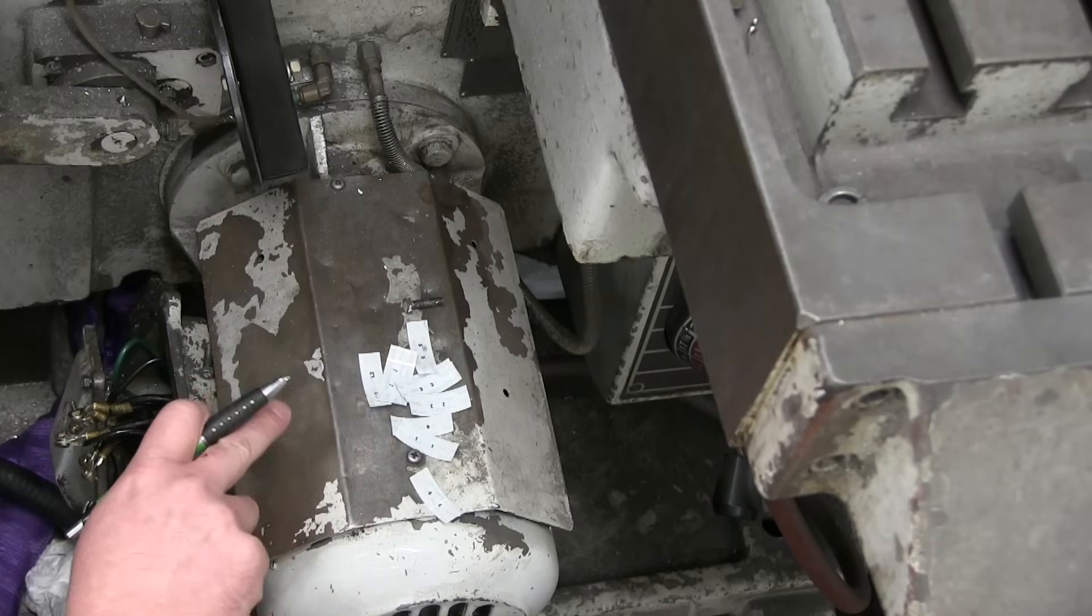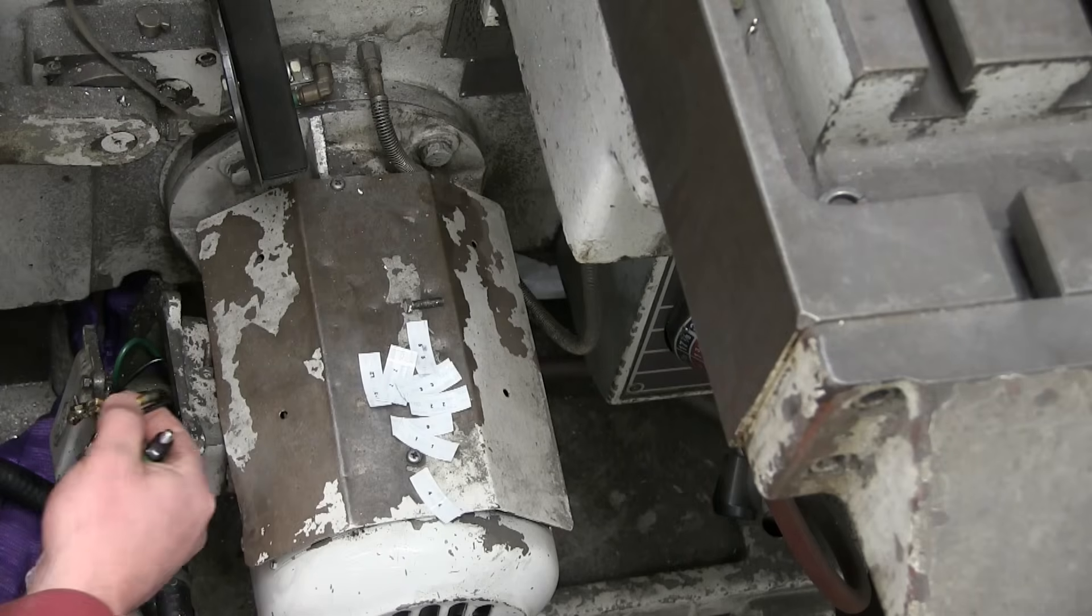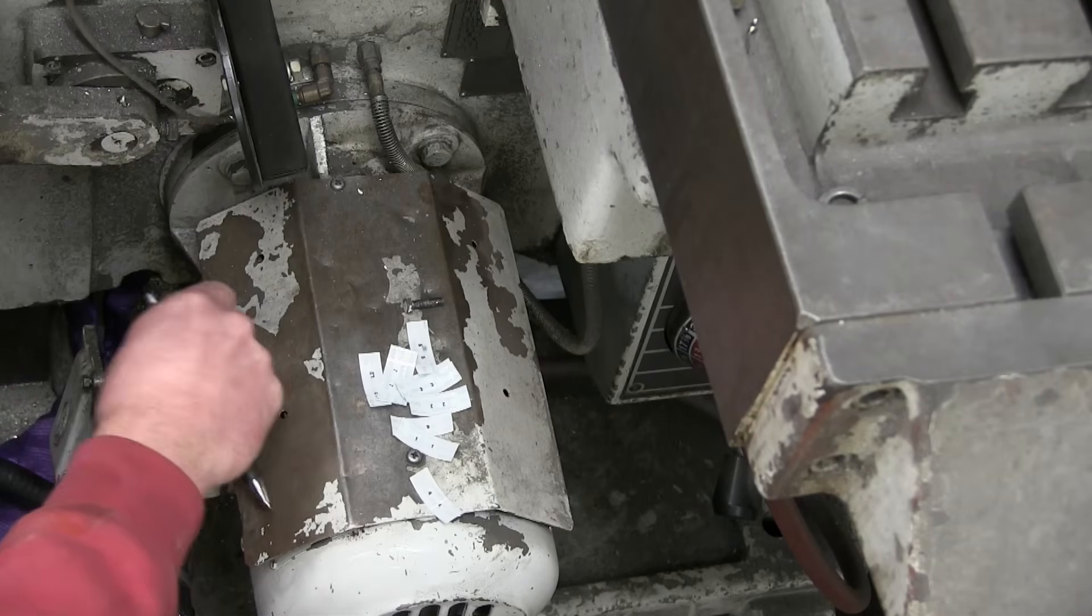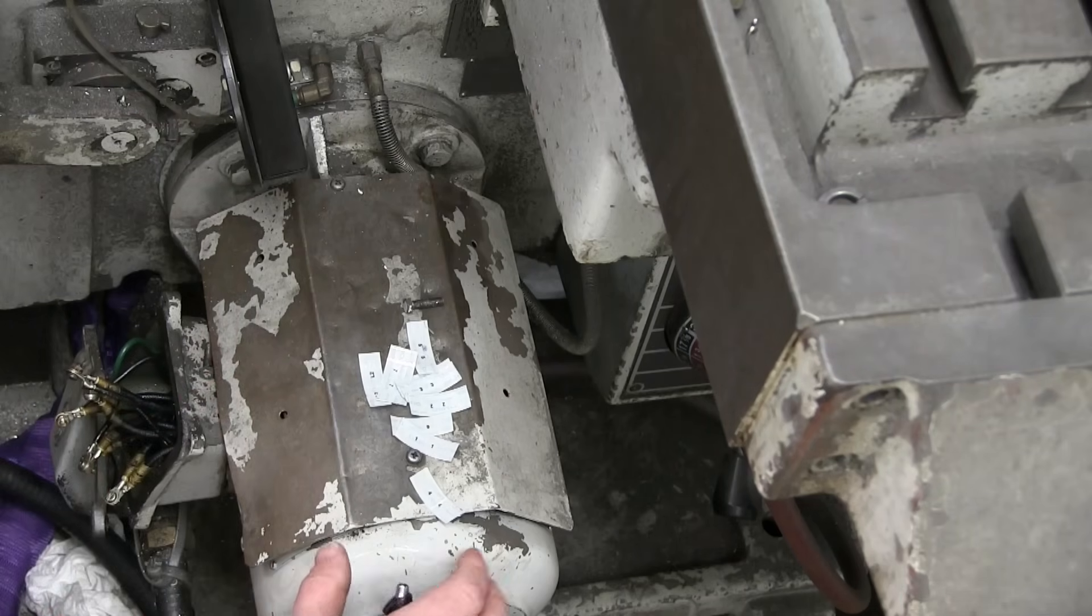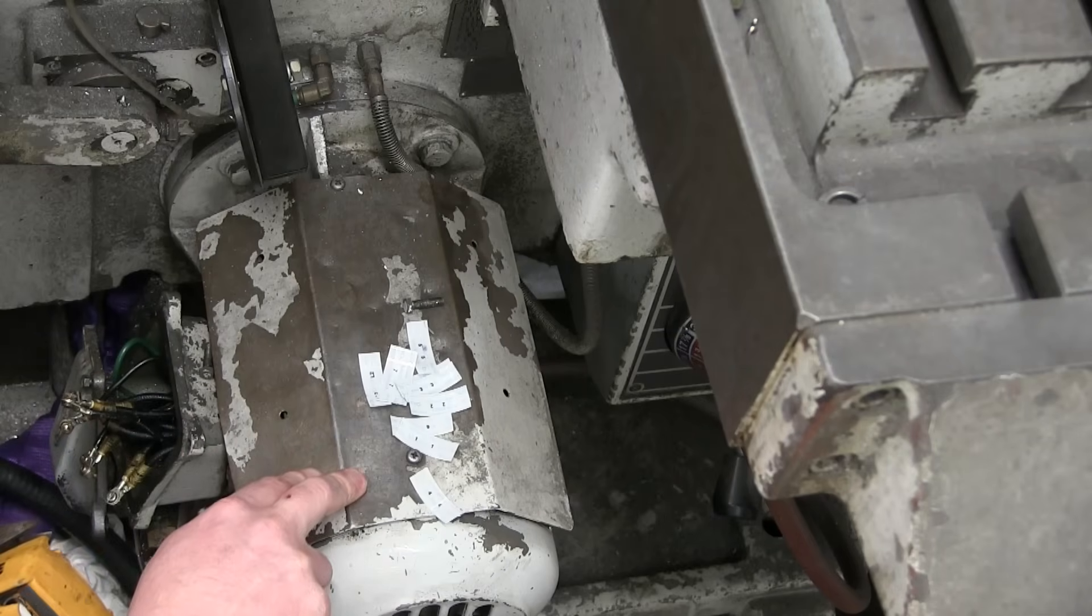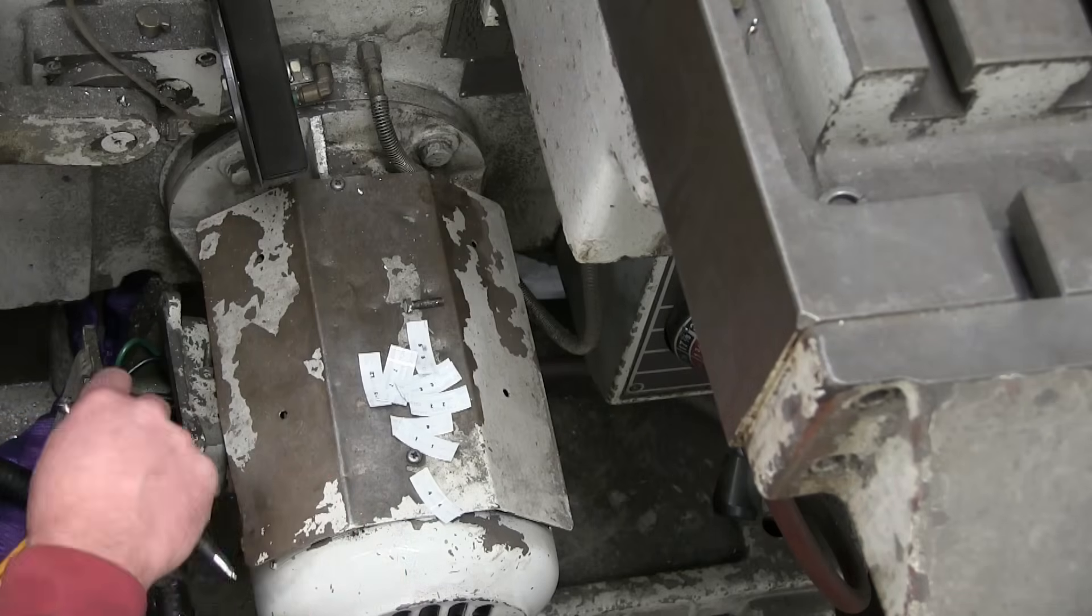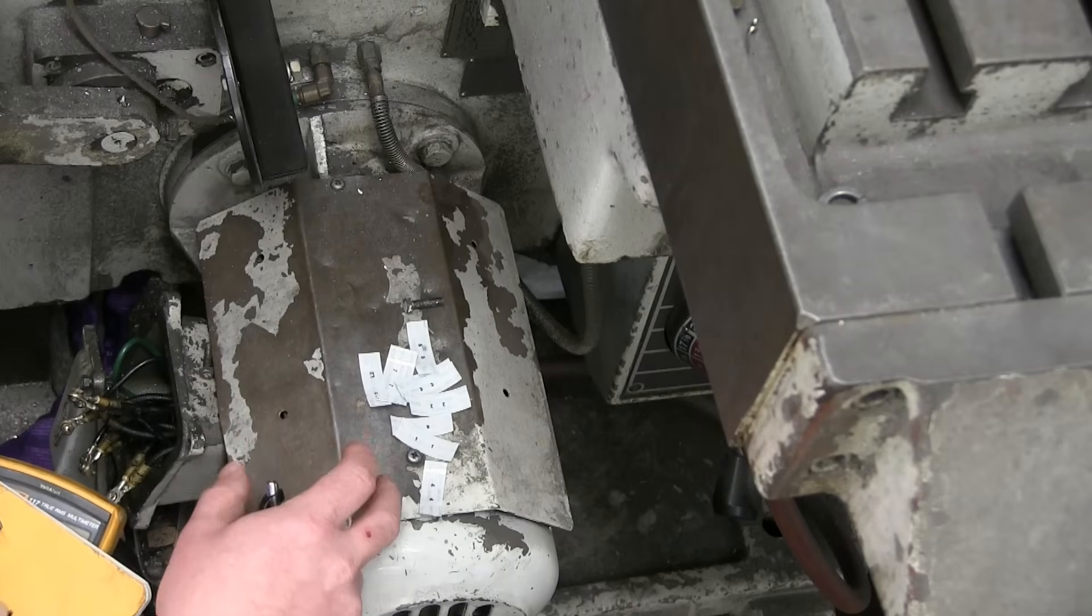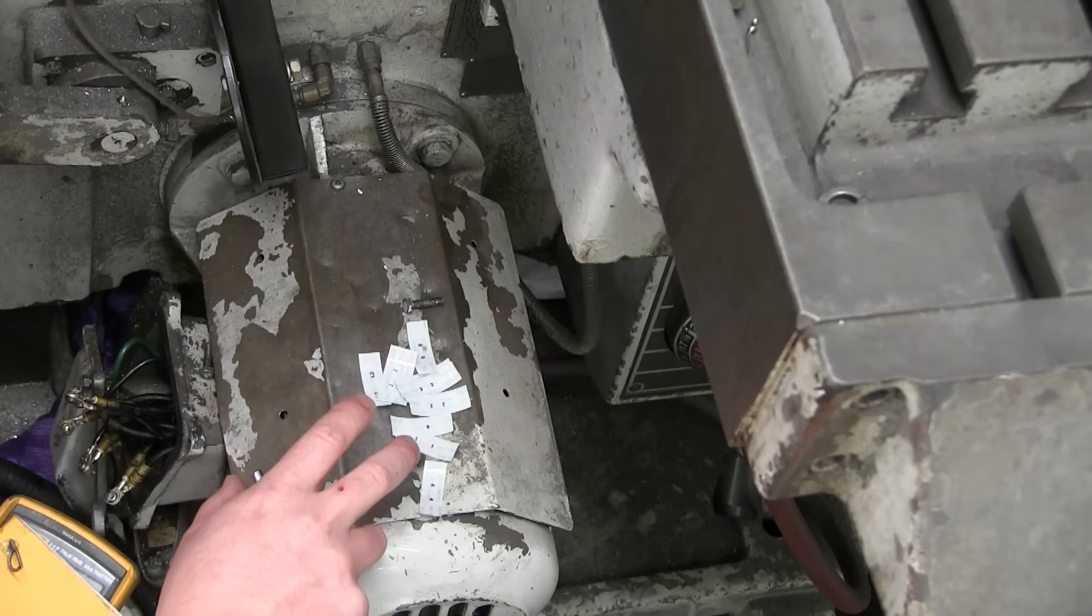Now I know this is a Y connected motor because it's on the nameplate. Also, as confirmation that somebody hasn't messed with this, there are three wires here and they all have continuity. That means internally they are all connected. So what we can do here, and I'll do a video about this: Delta connected, Y connected, how to troubleshoot, how to label these if you don't have any labels at all. Because a lot of times guys in the shop pick up a motor for cheap off eBay or whatever, and it's just a dog's breakfast. They end up wasting their money because they can't figure out how to wire it up. But I will show you that. We'll go on the workbench.